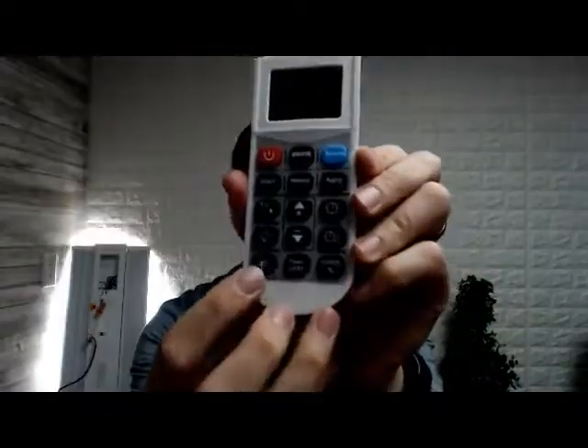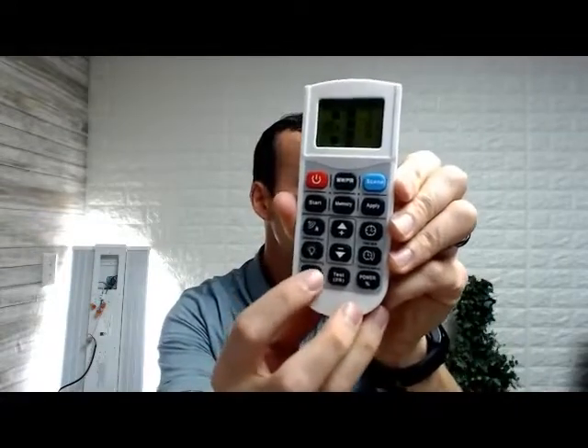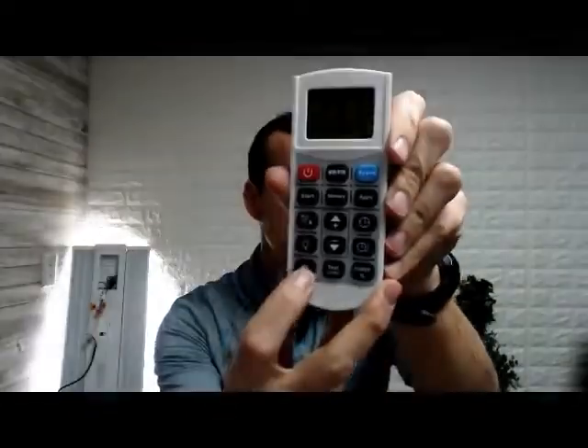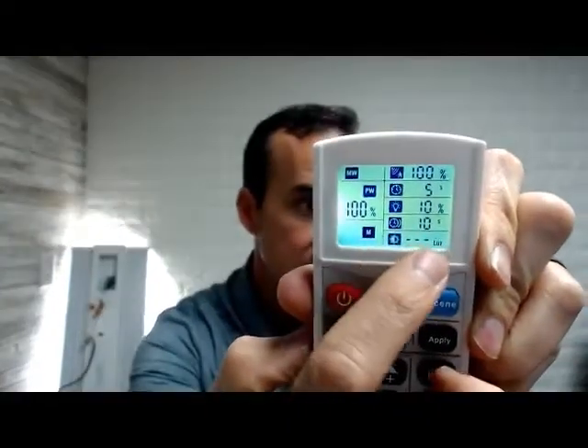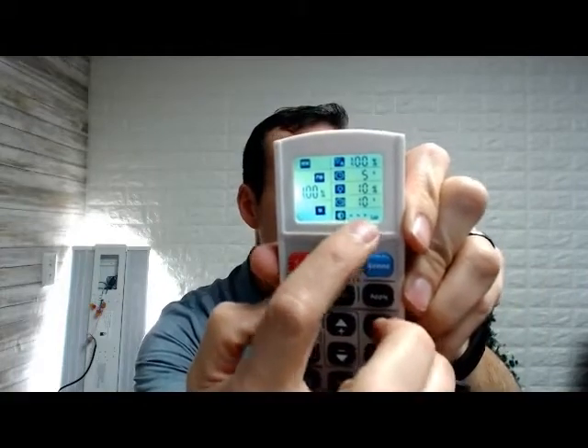You'll notice down here on the bottom, there is a daylight sensor. This is if your sensors have both daylight harvesting as well as motion, that's where you would use that daylight sensor. And that's in conjunction with the MWPIR piece, this MWPIR is a button you press, and it will automatically configure the light harvesting piece on how much light's currently coming through the window, and what it should be kind of set to. And then this piece here is where you can manually adjust. If you can see on the bottom, there is actually a line for the Lux right there, it's a little bit blurry. But the Lux right there is where you can manually set those pieces, really only if you have daylight harvesting in your sensors.